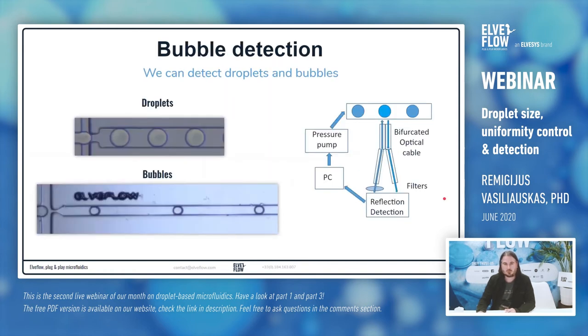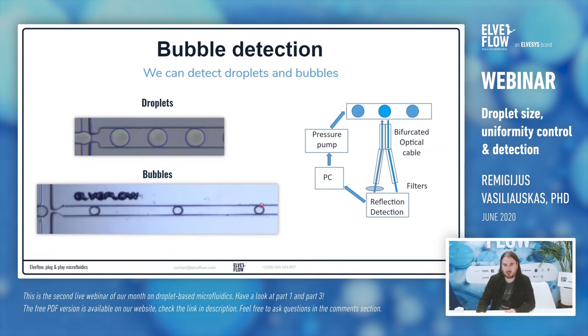We also noticed that many people work not only with droplets but also with bubbles. Looking with the eye, the difference between bubbles and droplets is minimal, but for the system the difference is significant. So we have modified the system to detect bubbles as well. Instead of collecting fluorescent light, we collect reflected light and don't use filters for fluorescent light. All other system parts are the same. Because bubbles have much better reflection compared to droplets, we can detect them even better.